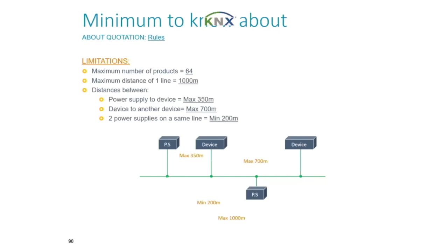There are some rules, as we've been talking about - I won't go into too much detail, because I don't know how technical everyone is - but basically we tend to stick to 64 maximum products on a line. It is possible to extend that, but you have to put in additional power supplies and so on. Typically, because we split things up into floors or areas, we're nowhere near that limitation normally. You can have 1,000 meters of line, big distances between devices on the KNX bus line.